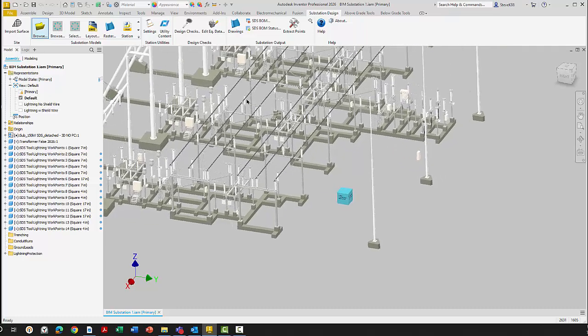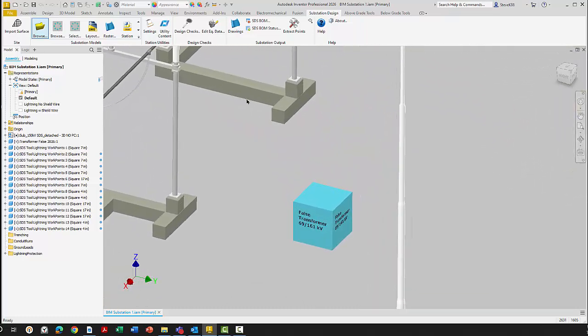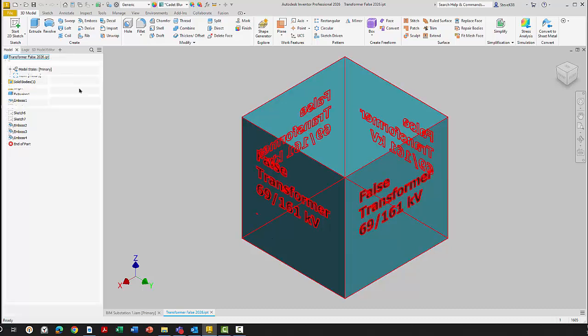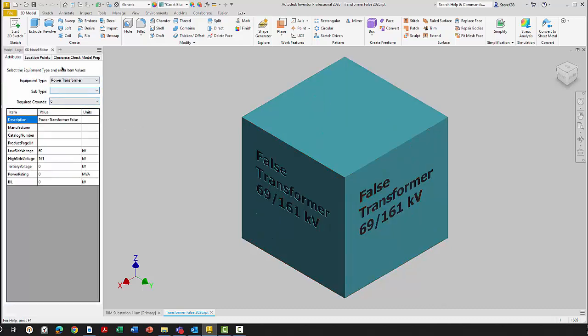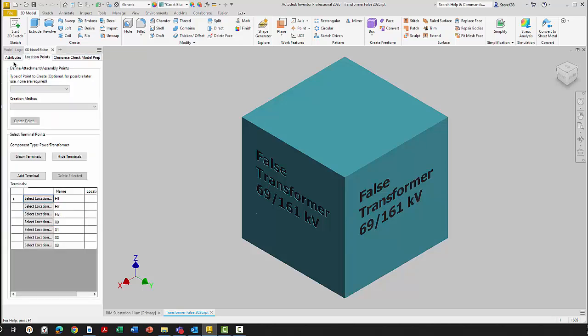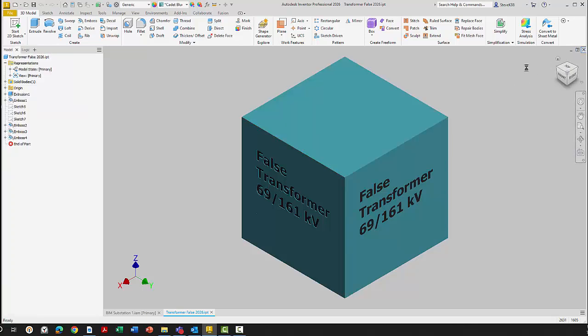What we need to do is add a transformer. In this case, we add a false transformer. It's just an IPT block. You can see the block is here. I'm going to open this block up. We have it set to be a transformer. I can look up in our SD model editor - it's called a power transformer. And the voltage is set here. So when we run our SDS design checks, on the high side it knows to check it to the 161 kV. There's nothing else I need to do. I'm just calling it a transformer block, just so we have it in our model.